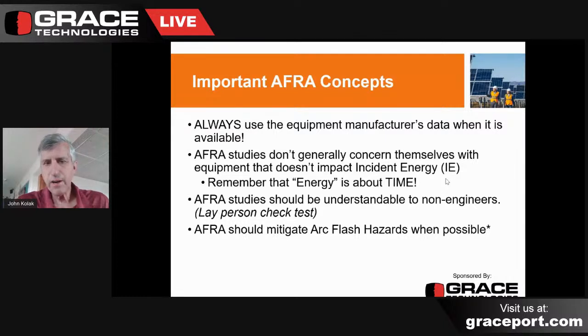So when we're doing an arc flash study, we're not really changing the short circuit current in most cases. What we're doing is changing how fast the system will clear a fault. And so that is a function of fault current and the relaying and things like that that are in play. So for the rest of the presentation, remember, when we're talking about incident energy, we're talking about a magnitude of short circuit current and a duration, an arc duration in terms of time.